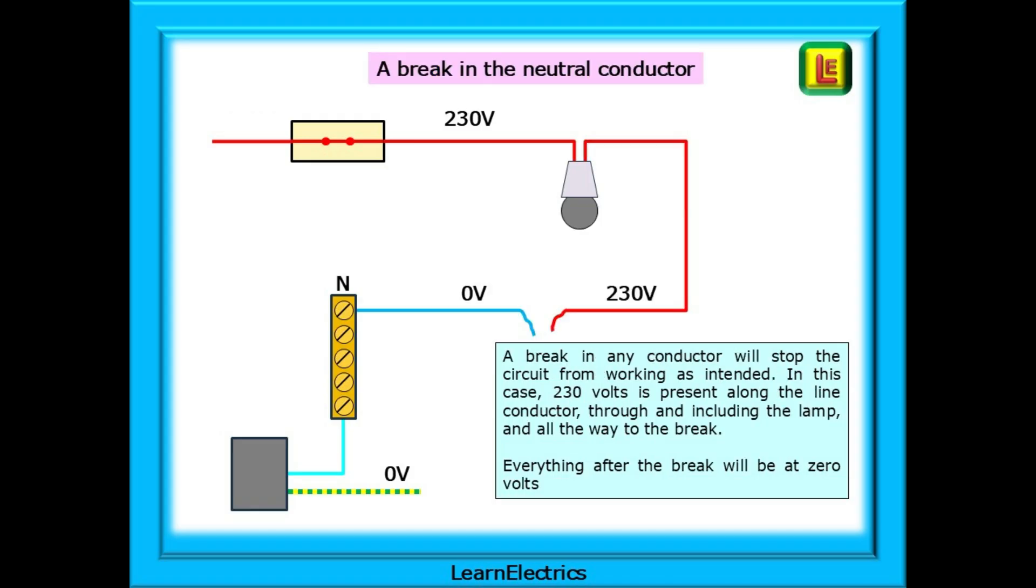A break in the wiring will stop the lamp from functioning for the same reasons. A break in any conductor will stop the circuit from working as intended. In this case, 230 volts is present along the line conductor, through and including the lamp and all the way to the break. Everything after the break will be at 0 volts. If there is no route to earth, then everything before the break would be at 230 volts or line voltage.